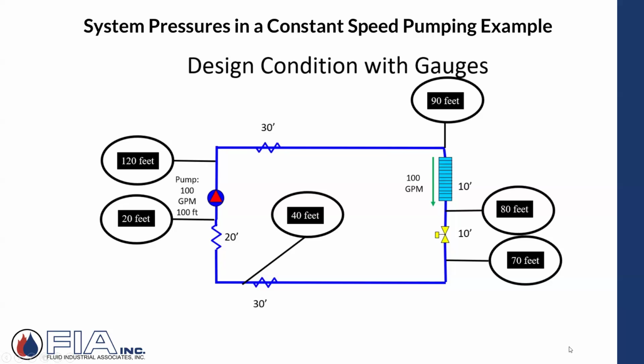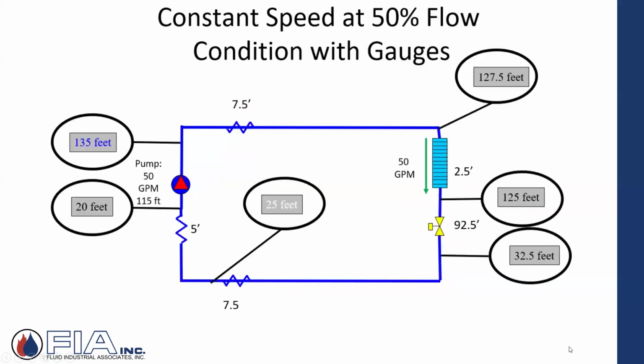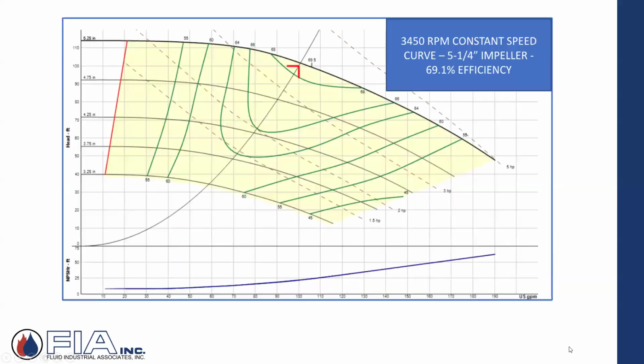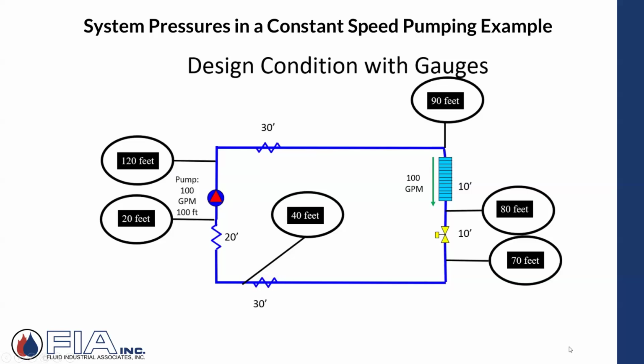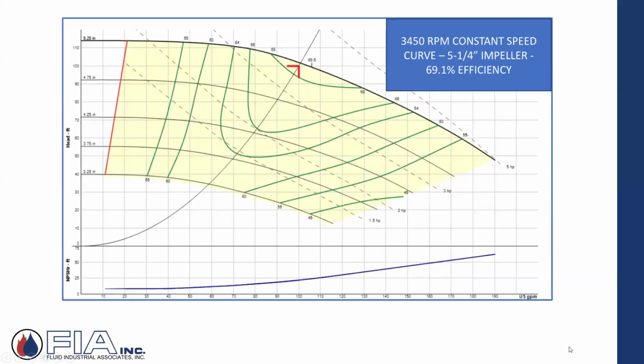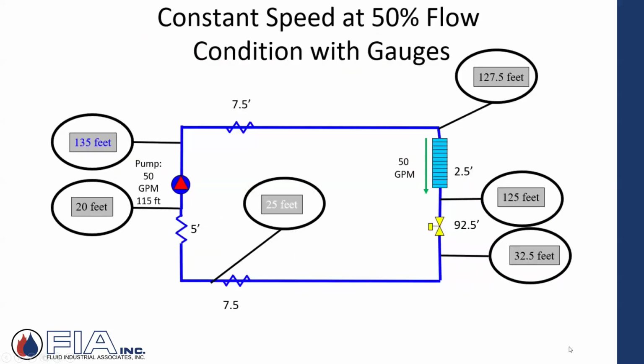And then all of a sudden, on scale 5, without moving the wheel, or if I was doing a little math calculation, now I have 50 GPM going through that same network. And I look and I say 50 GPM is 7.5 feet of head loss on scale 5. Huh, that's what it's listed here. Same thing on the coil. When I had my full flow, 100 GPM, I had a 10-foot head loss. When I cut that flow, so again, scale 5, 100 opposite 10, go down to 50, there it is, 2.5 feet of head loss. So that's very real. That's happening. You reduce your flow, you reduce your head loss.